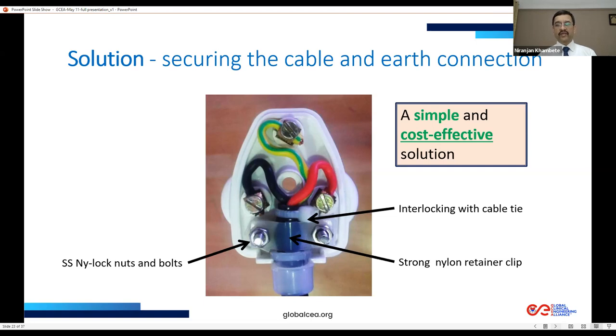Extra length is also provided to the earthing cable and neutral cables. This, I would say, is a simple and cost-effective solution to a chronic earth bonding problem. So even if we test the earth once every six months, we can be confident it will remain secure in between, even with the equipment in clinical use.